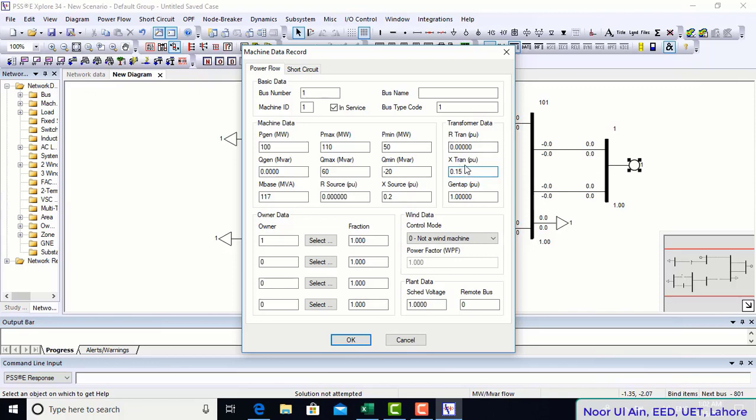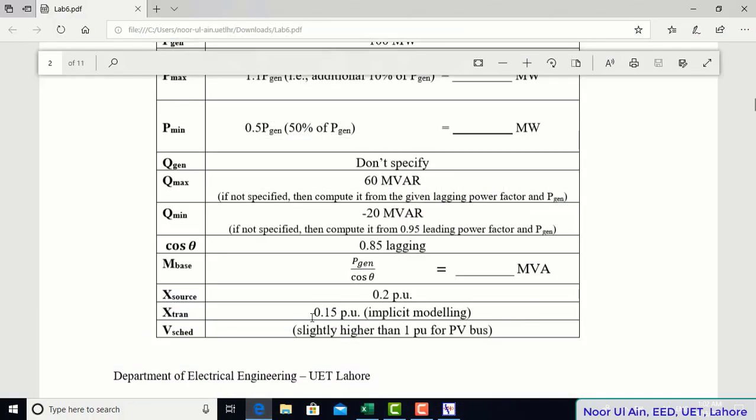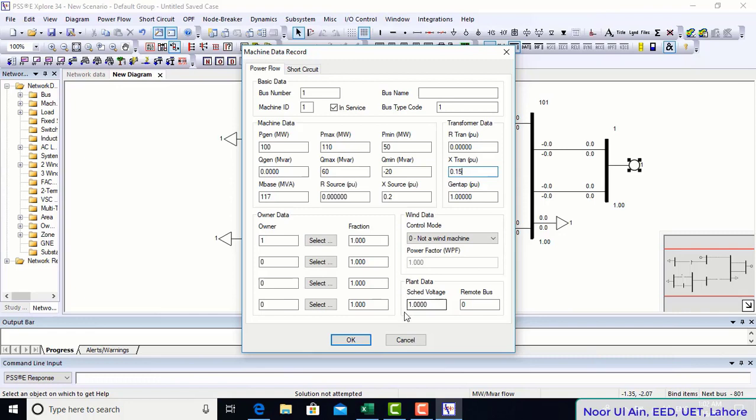What is implicit modeling? Implicit modeling is basically you cannot monitor the real and reactive power flow through this transformer. And usually the generator step-up transformer's reactance is specified within it. Right? Okay. What else? The schedule is usually kept higher than 1 per unit, but I'm not going to change it for a while. You can change it from here.